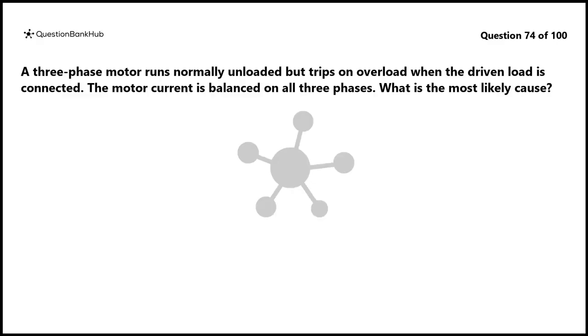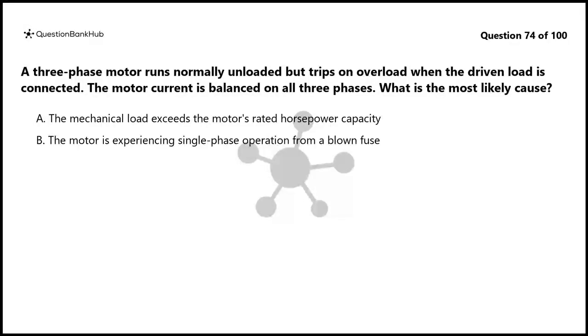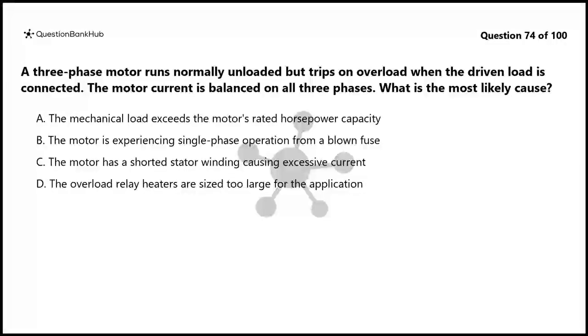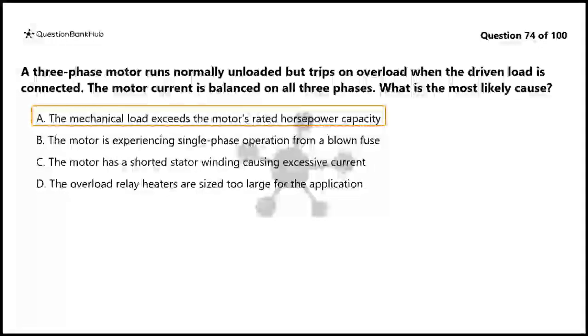Question 74. A 3-phase motor runs normally unloaded but trips on overload when the driven load is connected. The motor current is balanced on all 3 phases. What is the most likely cause? A. The mechanical load exceeds the motor's rated horsepower capacity. B. The motor is experiencing single-phase operation from a blown fuse. C. The motor has a shorted stator winding causing excessive current. D. The overload relay heaters are sized too large for the application. The correct answer is A.